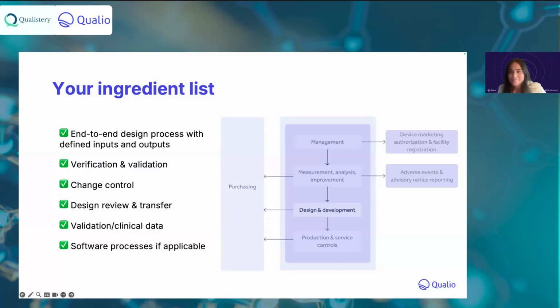Yes, correct. It's a broader question, but I will try to summarize and provide the key details. When you perform the verification step, you need to identify the test cases according to the risk associated at each level. For example, you have the design inputs and the design requirements which you have written. Based on that, you might have identified the risks, where all the risks are, and how you're going to mitigate them. Now you are also verifying to make sure that everything is taken care of and there aren't any major issues happening. Accordingly, you need to create the test cases in such a way, specifically if it's a hardware device, covering the acceptable quality limits, and to what extent something can be accepted and released to the next level. I hope I answered the question.